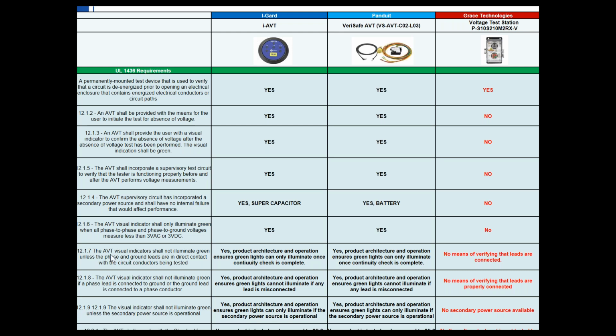12.1.7, the absence of voltage tester visual indication shall not illuminate green unless the phase to ground leads are in direct contact. Okay, so it's connected properly, yes. The i-Gard i-AVT performs this continuity test. The Panduit VeriSafe performs this continuity test. The Grace product does not comply. 12.1.8, the absence of voltage visual indicator shall not illuminate green if all phase indicators are connected to ground and ground leads are connected to a phase. Yes for the i-Gard i-AVT. Yes for the Failsafe. The Grace product does not comply.